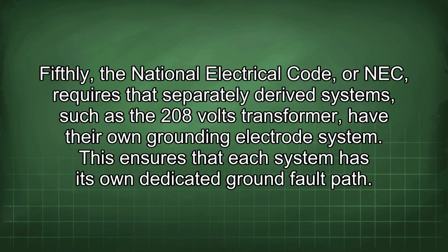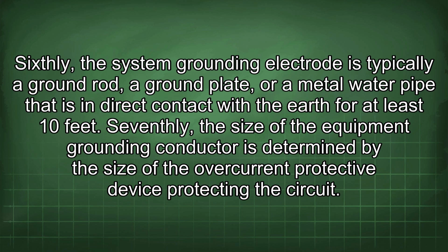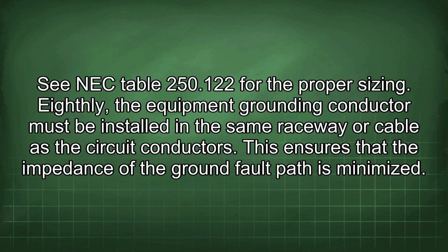Fifthly, the National Electrical Code, or NEC, requires that separately derived systems, such as the 208 volts transformer, have their own grounding electrode system. This ensures that each system has its own dedicated ground fault path. Sixthly, the system grounding electrode is typically a ground rod, a ground plate, or a metal water pipe that is in direct contact with the earth for at least 10 feet. Seventhly, the size of the equipment grounding conductor is determined by the size of the overcurrent protective device protecting the circuit. See NEC Table 250.122 for the proper sizing.